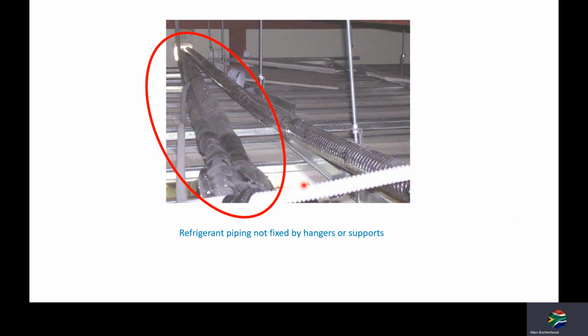Here I've highlighted refrigerant piping not fixed by hangers or supports, it's just lying loose in the ceiling. And ultimately this is going to allow for lateral movement, a left and right movement. Some of the refrigerant travels at between 2 and 6 meters a second through pipework, and ultimately with lateral loading you're going to create pipe fractures, especially on the bends where they come through, and you ultimately end up with a refrigerant leak.